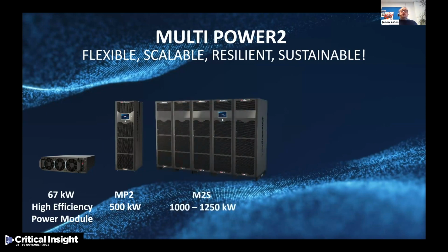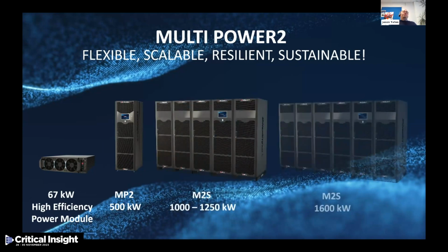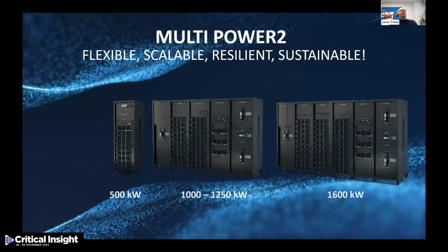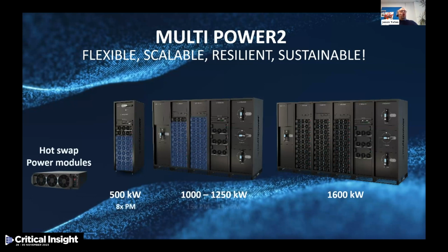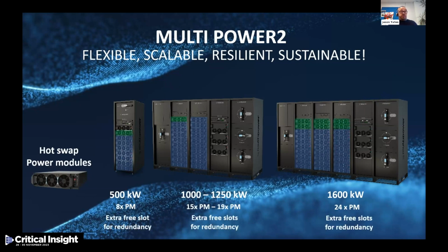We have a 1 meg to 1.25 meg power frame, and then we have a 1.6 meg power frame. Now, basically, these cabinets can all be connected in parallel with more power frames, so we can increase the power still further. If we take a look inside these cabinets, you can see they've all got a very, very similar layout, but they're built around the hot swappable power modules that can fit inside all of the cabinets. The same power modules are used throughout all cabinets. There is space for redundancy for redundant systems. They have a fully rated bypass system in the eventuality of problems.